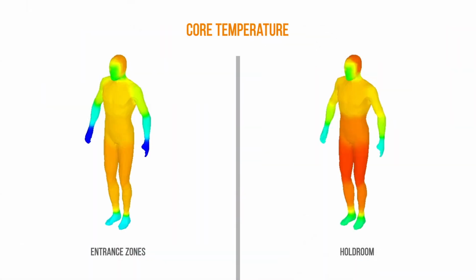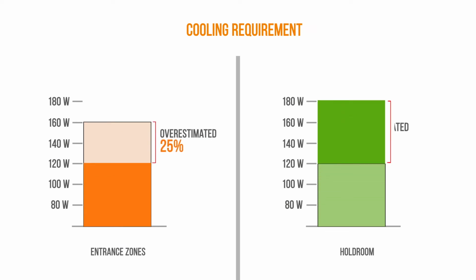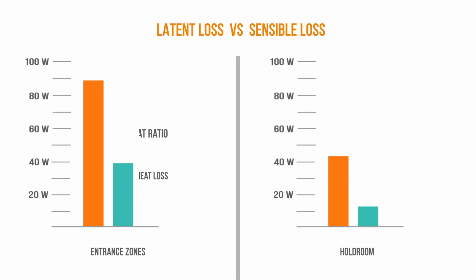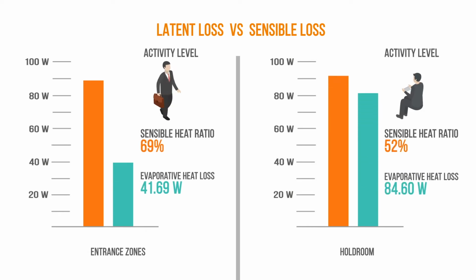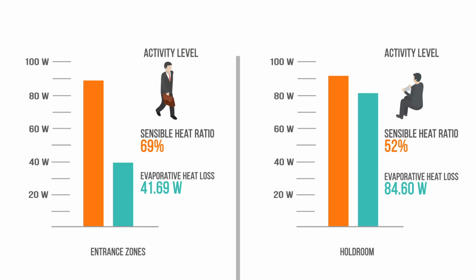Comparing the core temperature distribution in the entrance zone with the hold room clearly indicates heat storage in the body. Due to this, the cooling requirement is overestimated in the entrance zone while underestimated in hold rooms. Similarly, the sensible heat ratio varies from 69% to 52%. Thus, the precise prediction of heat exchange becomes critical in terminal buildings.